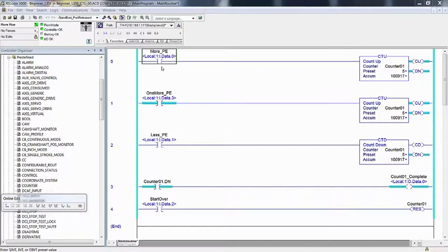What's happening here? This rung is false. So the false execution of a count up is to reset its one shot that allows it to increment only once on a false to true transition. But the very next rung is true, so it increments. And then the next scan around sets it to false, sets it to true, sets it to false, sets it to true. Well, the question was, what happened? I just explained it. What is the moral of the story here?